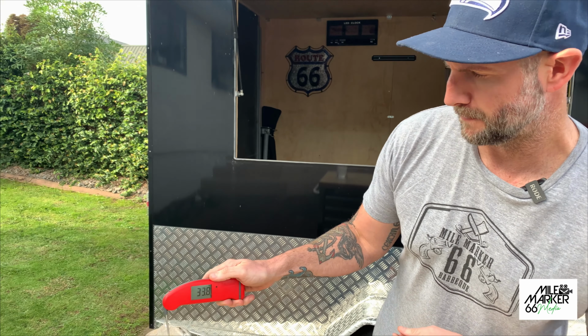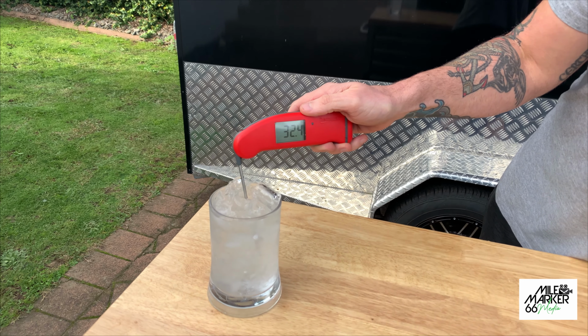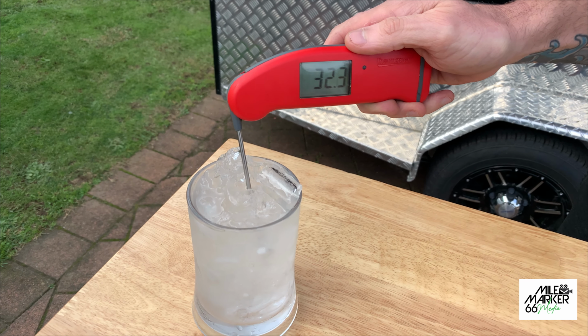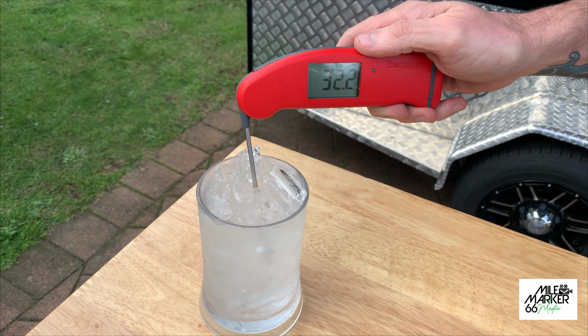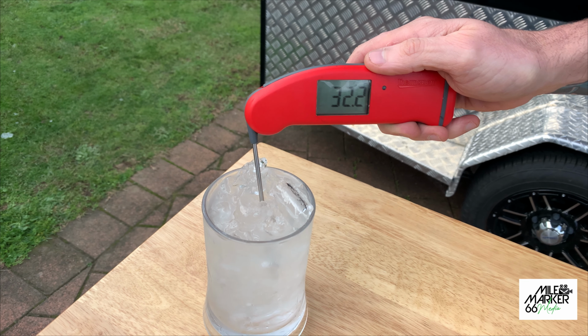They're all brilliant. So let's go through how we can validate and calibrate your instant read if it has that function. First one we'll look at is the Thermapen. Now, as I said before, we can't calibrate it, but what we can do is validate it. So what we've got here is a cup of ice. We've filled it up a bit with water, and we're presuming that that's our 0 degrees or 32 degrees Fahrenheit, the freezing point of water. So we're going to use that as our baseline. So you can see there again that our Thermapen is very quick to respond and very accurate too, 32.2, 32.3 degrees Fahrenheit. So it's only 0.2 or 0.3 of a degree Fahrenheit out. Right, now we're going to check the Inkbird.